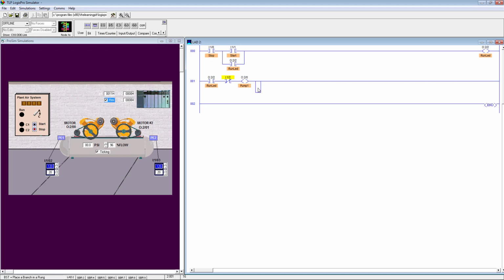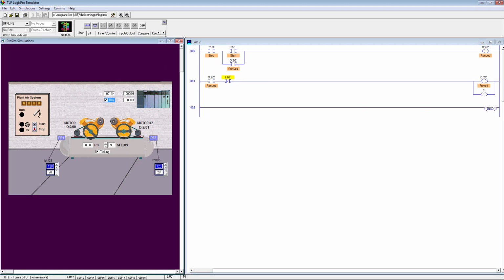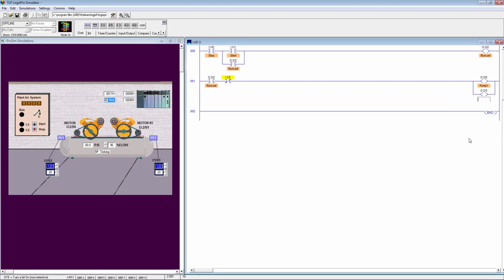So in order to implement that, we need to bring a feedback loop over here, and the corresponding LED indicator is C1 LED. Okay, so till now I hope this should work, and we need to adjust the flow rate. It should be 50% before that. So let's turn it to the programming mode, program, run, click start, and you can see it was below 120, it was not up to the mark. So C1 is running, and it's trying to maintain the storage tank pressure.